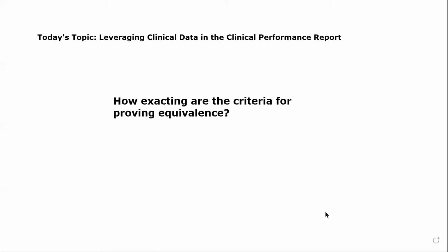So it's not something that you can just sort of skip through or rush. It's definitely a very exacting process. And in order for clinical data to be considered relevant, the equivalent device also should be CE marked and used in accordance with its intended purpose as documented within your IFU. So it's a very challenging process. And again, I would definitely defer to the guidance provided by MedDev in order to obtain specific information about how, if you're going about establishing equivalence, how to do that properly.